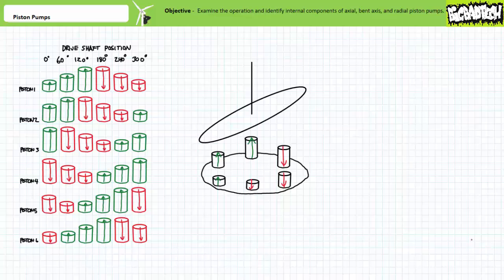Note I've drawn six pistons in this diagram to keep things simple; however, most piston pumps are manufactured with an odd number of pistons. The axial offset of the swash plate from the drive shaft determines the volume of fluid introduced to the system each turn of the drive shaft. If the swash plate angle remains fixed, this would make a fixed displacement piston pump. If the angle of the swash plate can be varied, this would make a variable displacement piston pump.